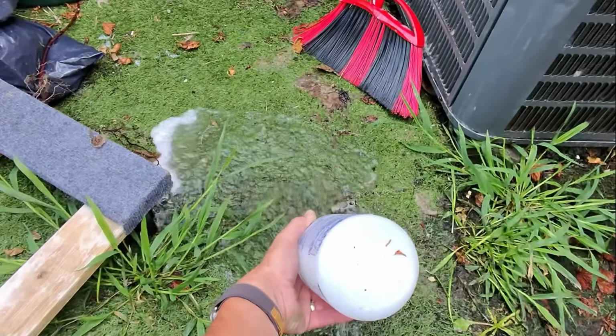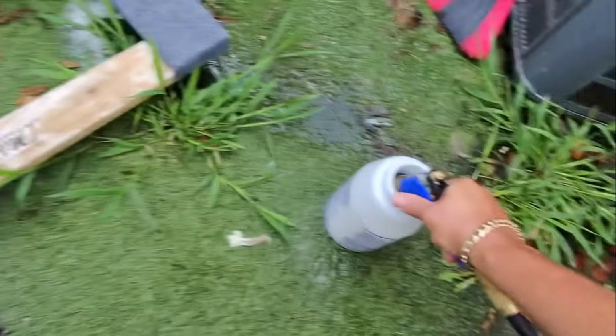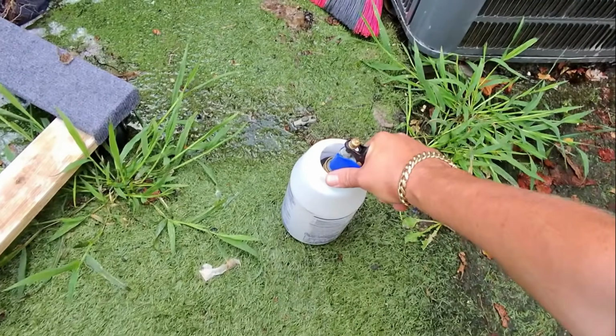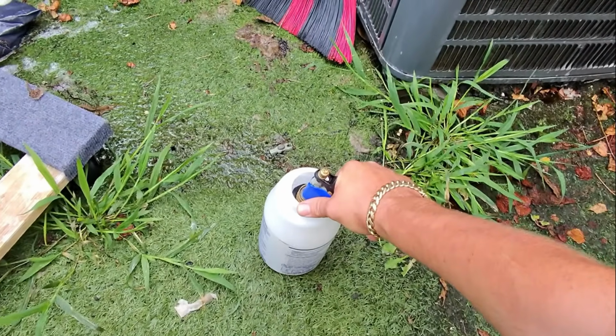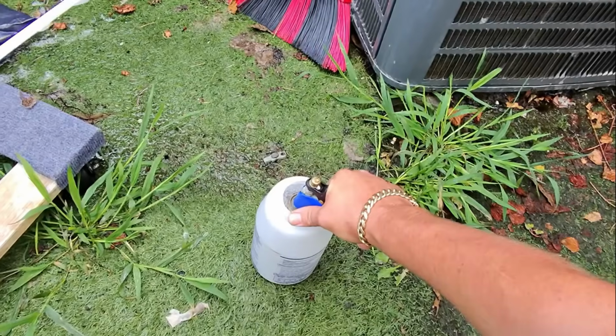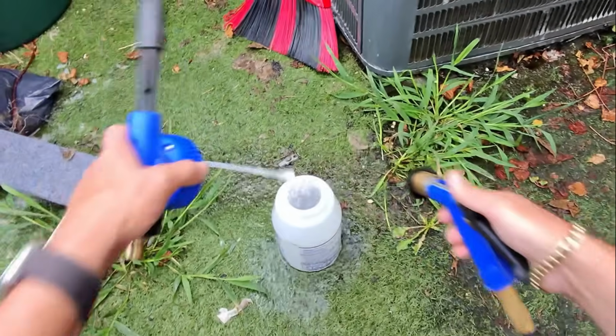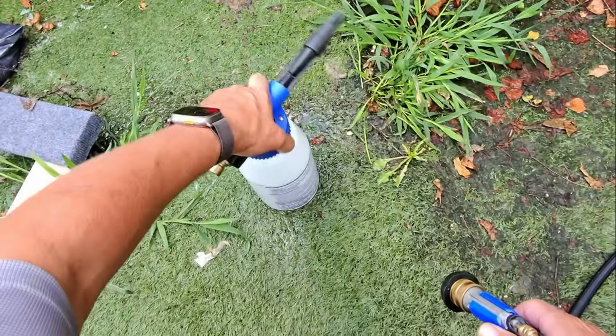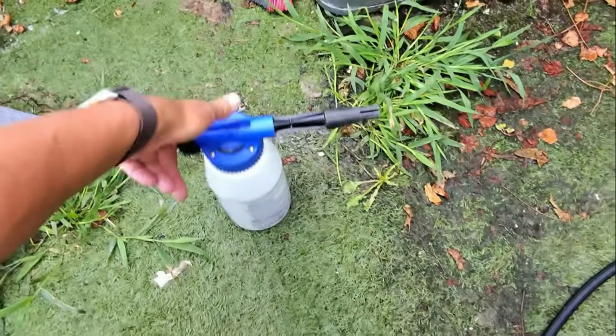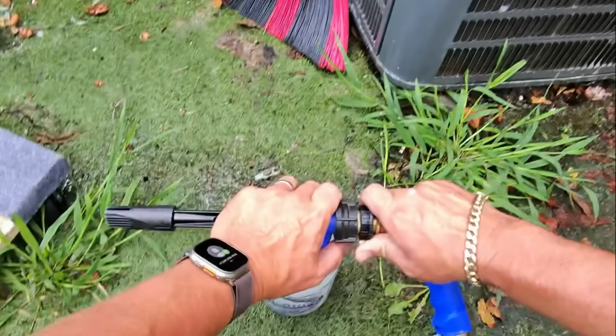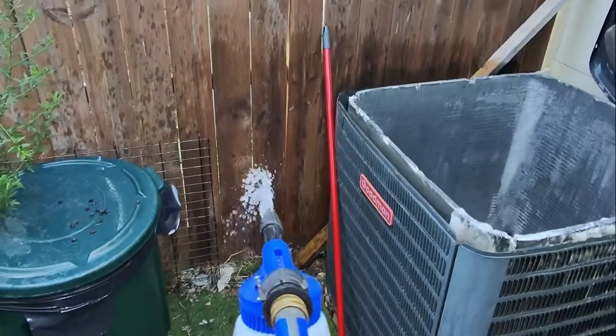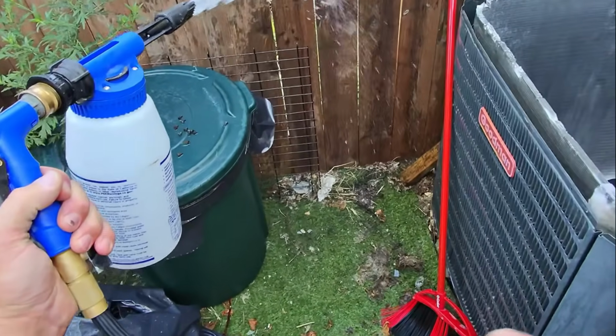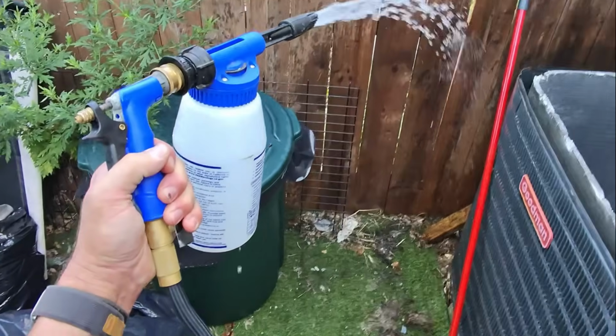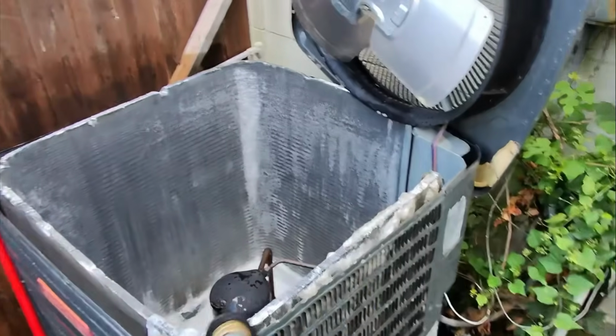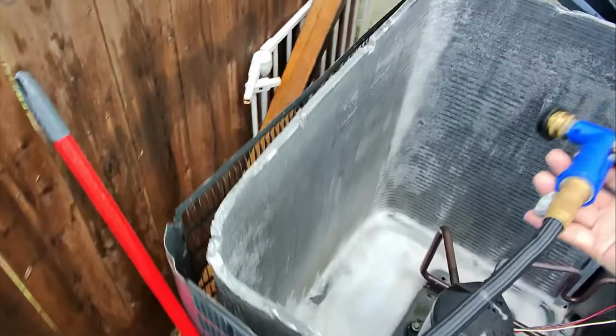I'm going to rinse out my container, make sure that it's going to be good for use the next time I need it. If you don't thoroughly rinse out the foam gun container and the foam gun by running water through it, next time you use it, it is not going to be functional. Now, I say this over and over and over again in all my videos. Every time I'm doing a coil cleaning with a chemical, it is especially important if you're using the new Calgon Nu-Brite that you must thoroughly rinse it out. All right, it's time to rinse.